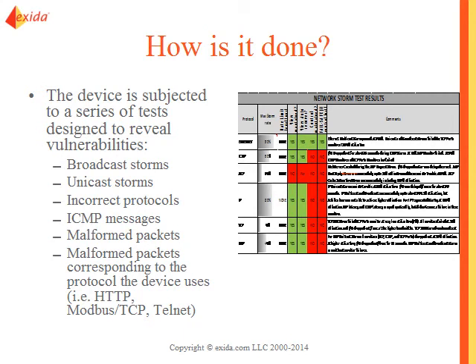So if this was part of an SIS, then this certainly would not be something that we would want to see, because it would give you a potentially dangerous situation. Even if it was a redundant system, if the software was the same in both and you had the same problem, then you would lose the redundancy in the case of this particular type of test. And normally we would do these types of testing on the shop floor or on a system that was offline. You wouldn't want to do these types of testing with systems that were online for obvious reasons.